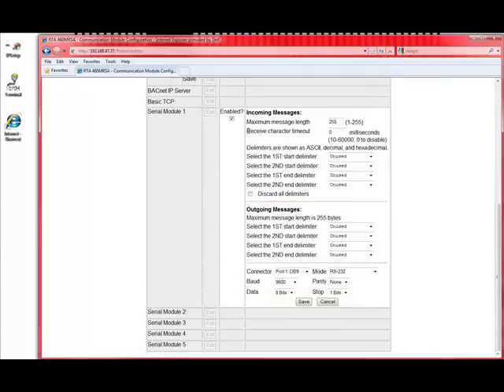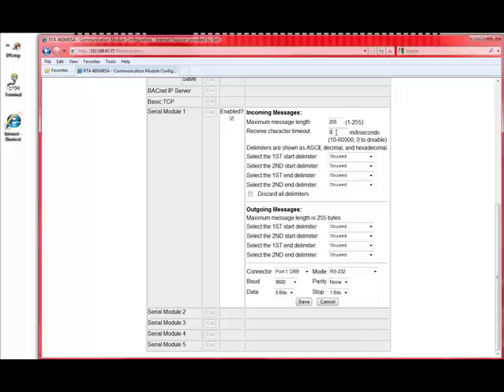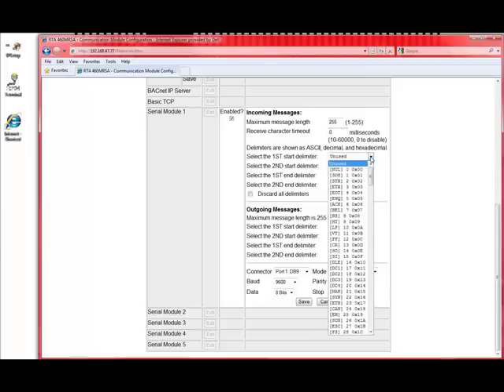Now we can enable it and unenable it, and we want it enabled. The maximum message length, this is the maximum number of characters that you have coming in on ASCII. That's set to 255. If it's less than that, it doesn't matter, so there's no particular reason to change that. Receive character timeout is how long to wait before essentially identifying a message. That's not good to use because it can easily get out of sync. So many people don't use that, leave it at zero to disable it. The way you could use that is, if you knew that every 100 milliseconds you're going to get in some number of characters, then that's the message that you want to move into the PLC.